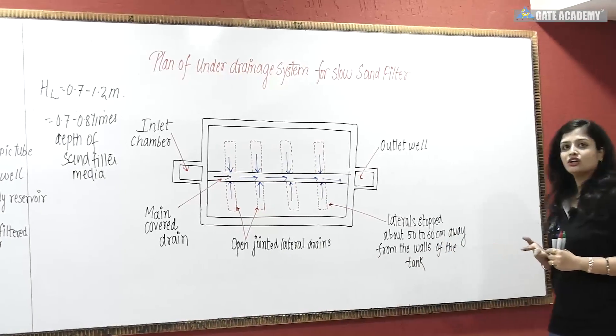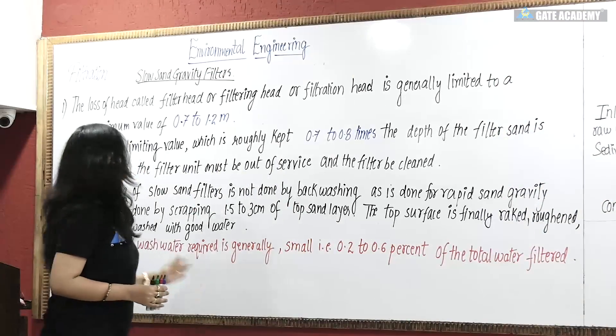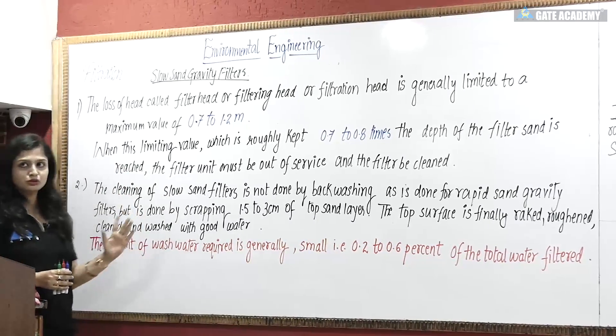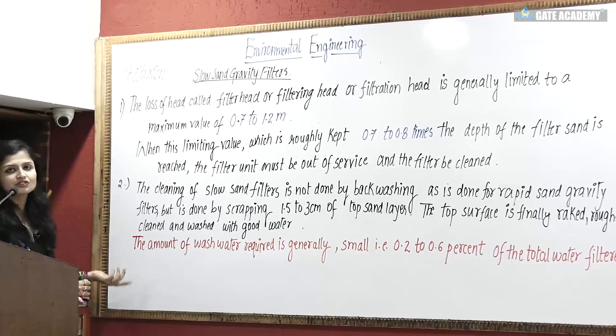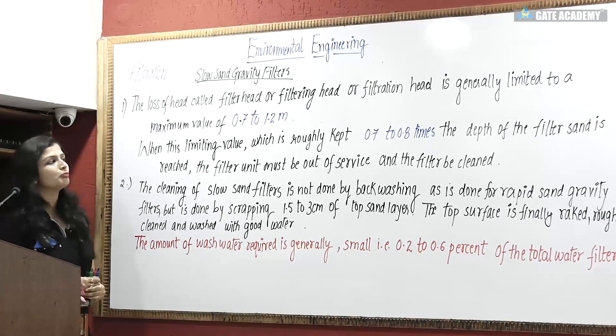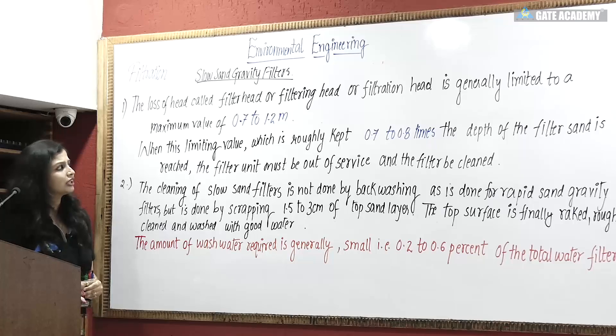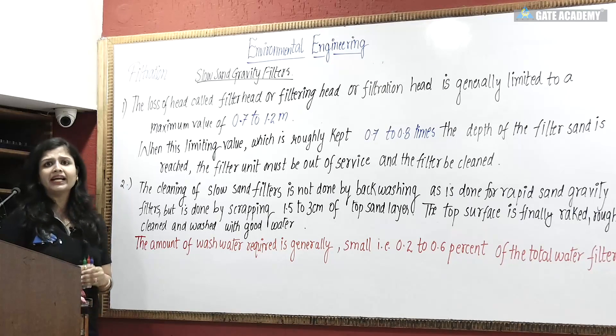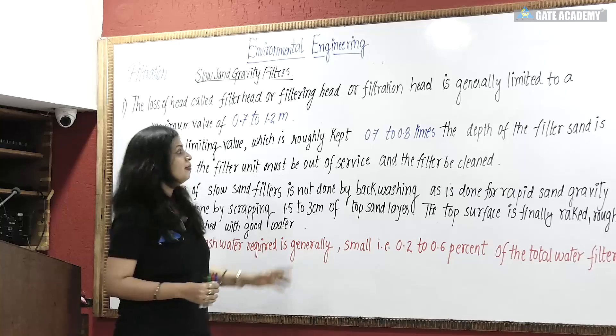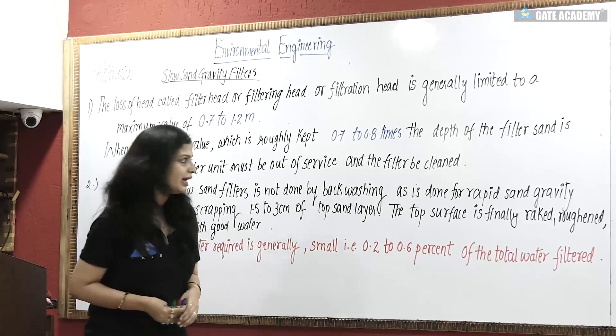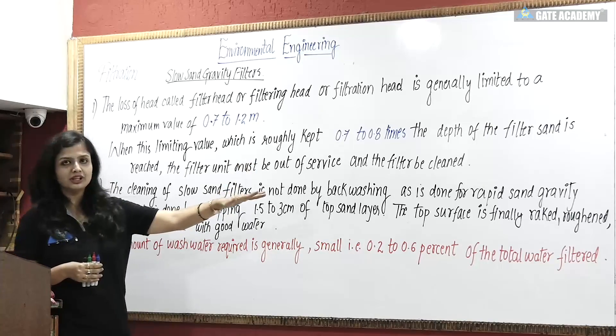Now let's note down the important points. The loss of head, called filter head or filtration head, is generally limited to a maximum value of 0.7 to 1.2 meters. When this limiting value, which is roughly 0.7 to 0.8 times the depth of the filter sand, is reached, the filter unit must be taken out of service and cleaned.